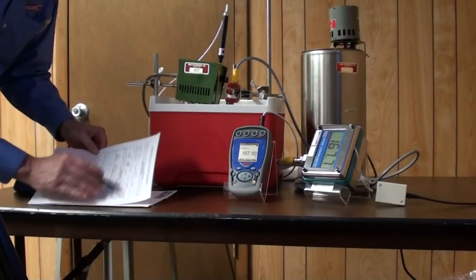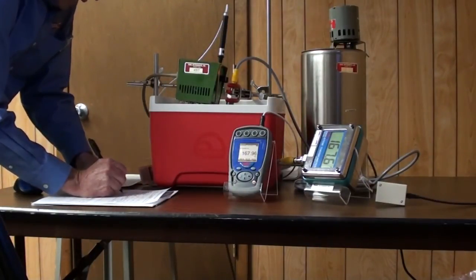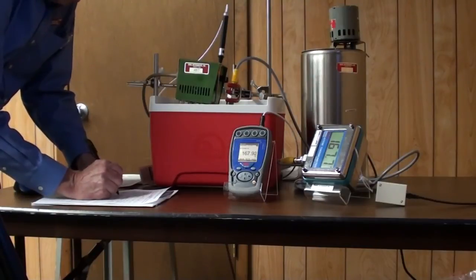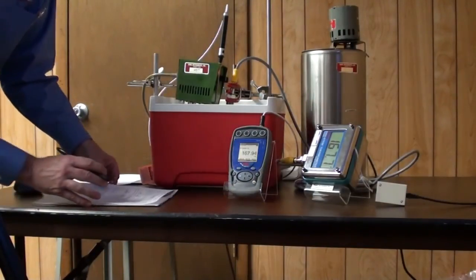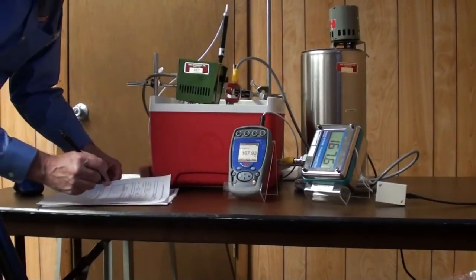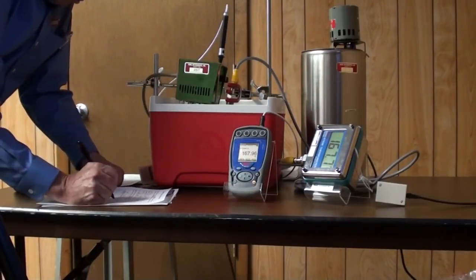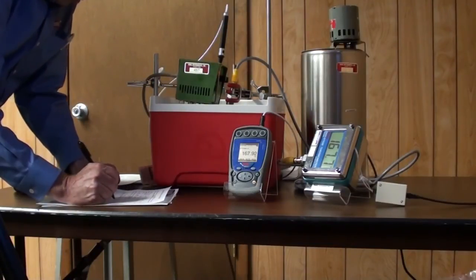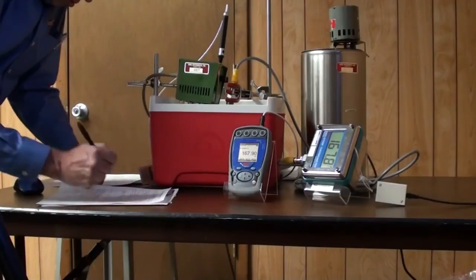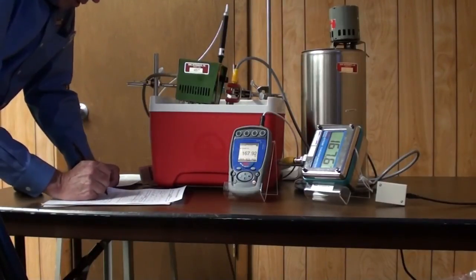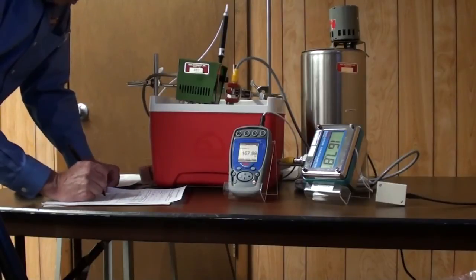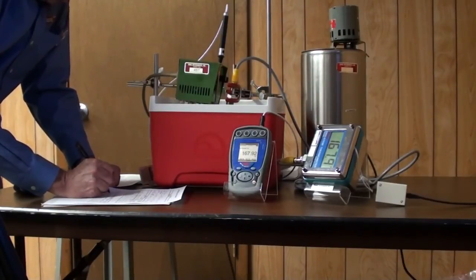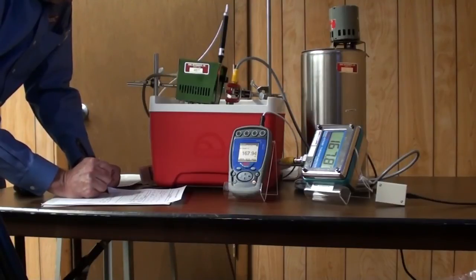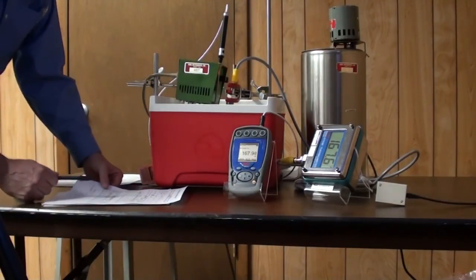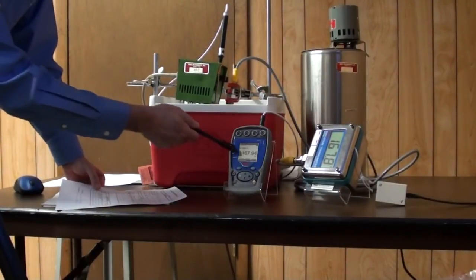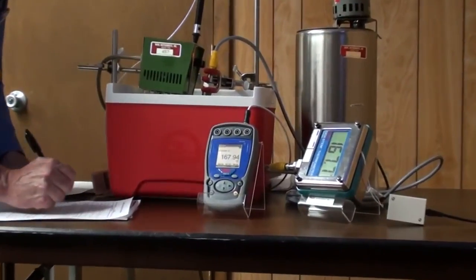And again, we'd record our temperature and humidity. I'm in a water bath, and my nominal temperature is 170 degrees F, and we're getting close to being stable there. My allowable deviation is going to be, before's 0.3, after's 0.2. Standard instruments, the same thing: it's a TM612, some serial number, RTD meter and probe. Okay, so if we take this now, my actual temperature is 167.94.